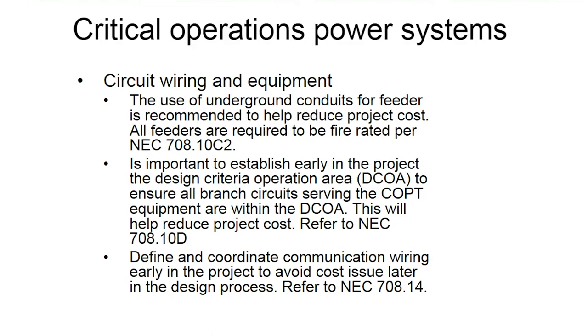Let's talk a little bit about wiring and equipment. I think this is very important. One of the things that we have been learning with this 708 is that it's a good idea to run feeders underground, because that allows you to keep your feeders protected. Many of those feeders will have to be fire rated per NEC 708.10 C2. And if you run them underground, you will be able to find some good cost savings. So that's just a recommendation, something that we have learned.